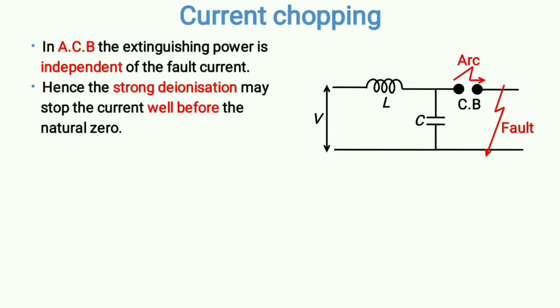Because the extinguishing power is independent of fault current, even if the fault current is small in magnitude, the extinguishing power remains very high. This results in an abrupt fall of fault current to zero. The current is supposed to be stopped at the natural zero point, because at natural zero the arc gets vanished automatically — that is the concept of the natural zero method, also called the low resistance method.